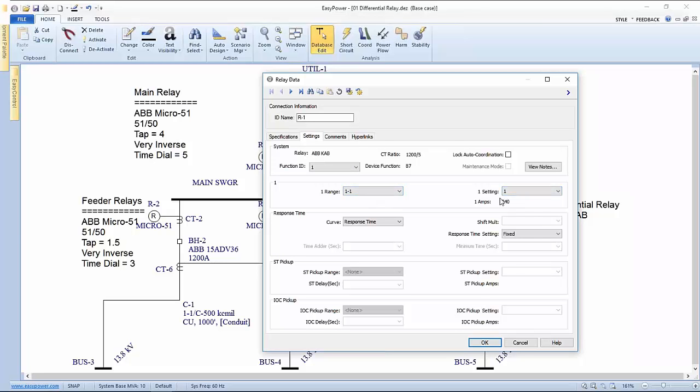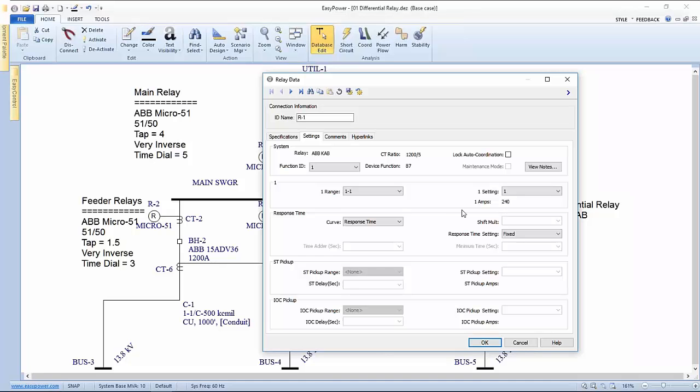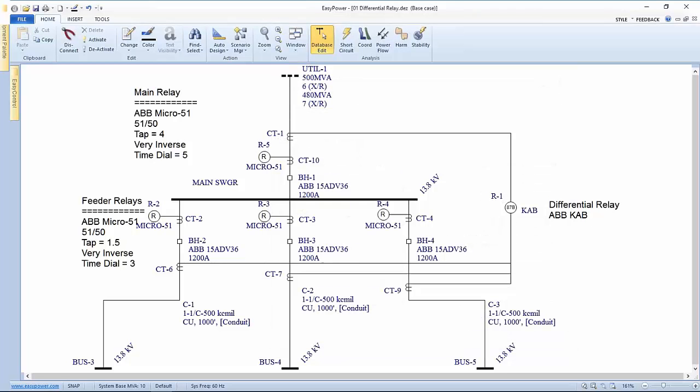Let's say this is still a two cycle delay for the relay or the breaker. When we go into settings, we see that this has specific dial settings. The significance here is this can be set up based upon the CTs that we're using to a relatively low level of current. And the response time is fixed based upon the operation time of the relay. This doesn't tell us anything about how long that fault may last. It's just that once that level is reached, the relay is activated. It's a time independent element. And it's not something we can accommodate in a flat device like a short circuit study.